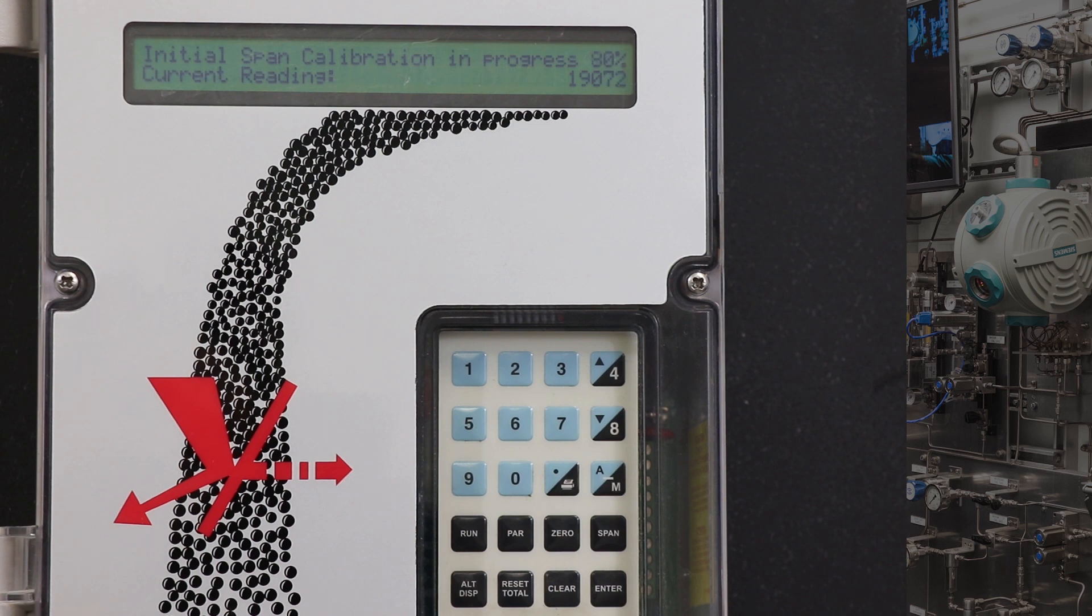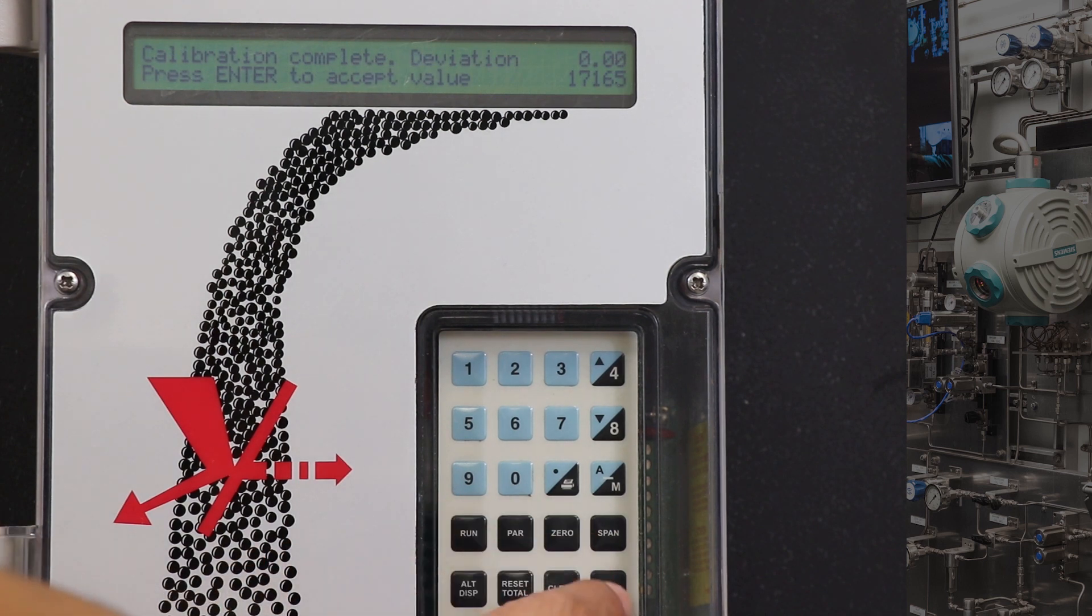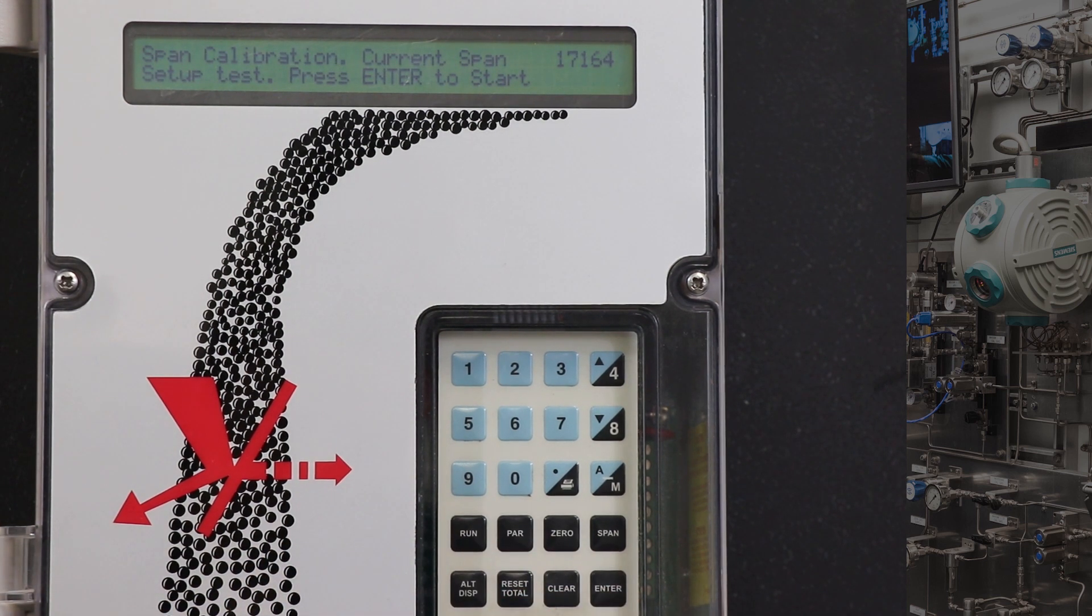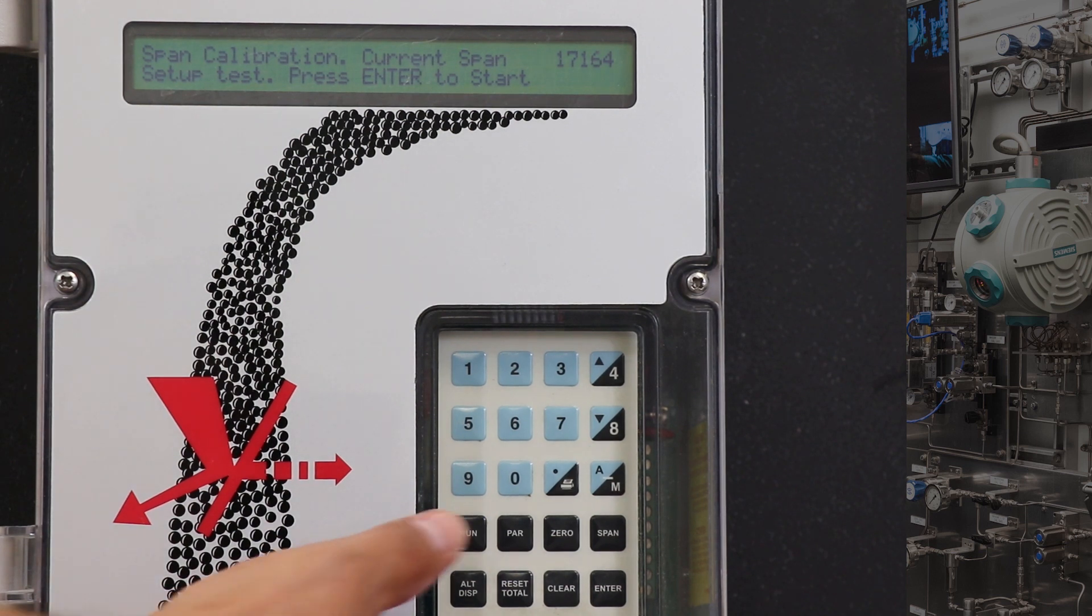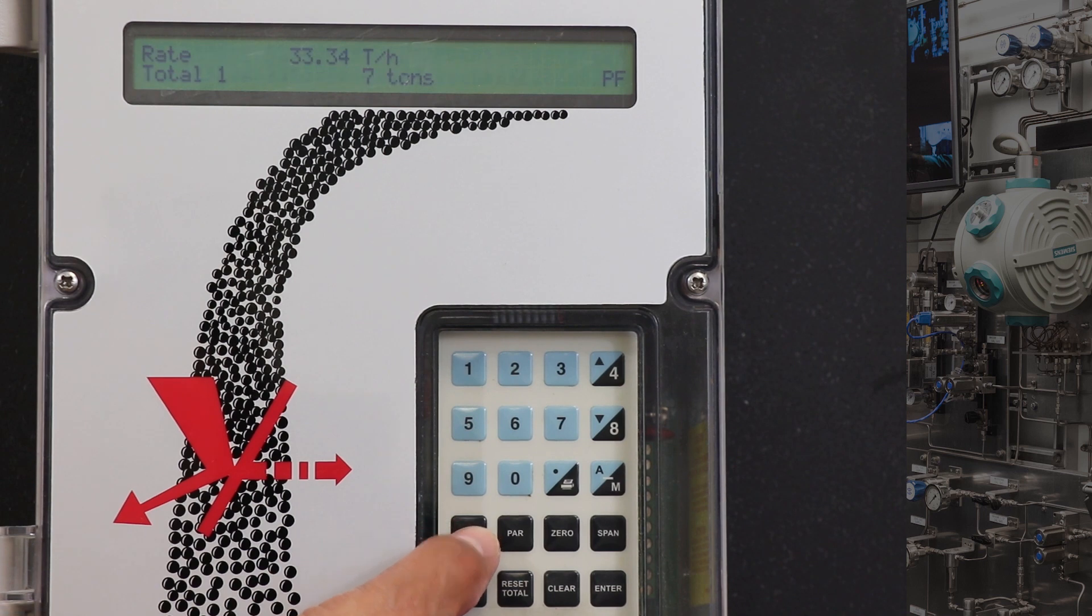Once the span calibration is complete, hit the enter button to set the span value. You can now go into the run mode by pushing the run button. Under rate, it should read what the test weight represents in tons per hour. Now remove the test weight and string and store them away.